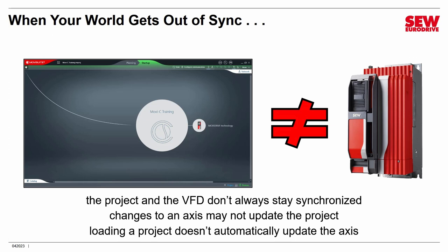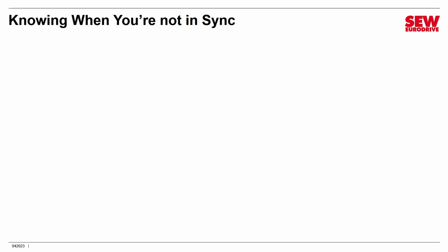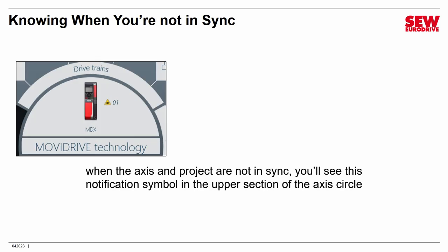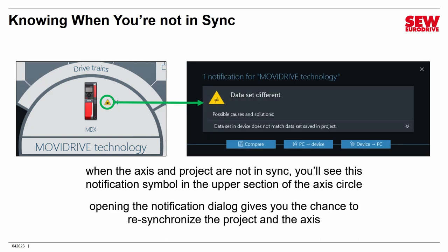And I'll just add an extra note here that loading a project doesn't automatically update the axis necessarily. There are times when a project is loaded into MoviSuite, but it is not propagated into the VFD. So how do you know when the situation exists and how do you deal with it? Well, happily, MoviSuite's pretty intelligent about it and lets you know. How do you know when you're not in sync? Very simple. You're going to see this on the axis circle. It's a symbol that appears. So when the axis and the project are not in sync, you'll see this little notification symbol. It's a yellow triangle with a not equal sign in it in the upper section of the axis circle. When that happens, it means that MoviSuite has detected that what it's got in its project and what's in the axis don't match.